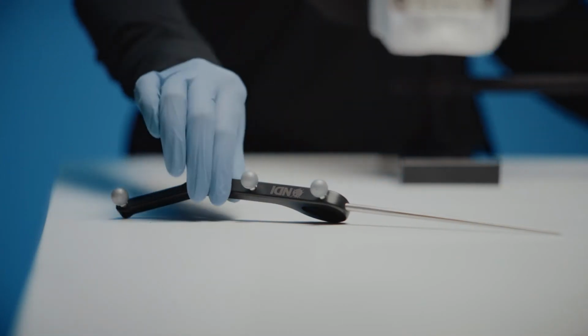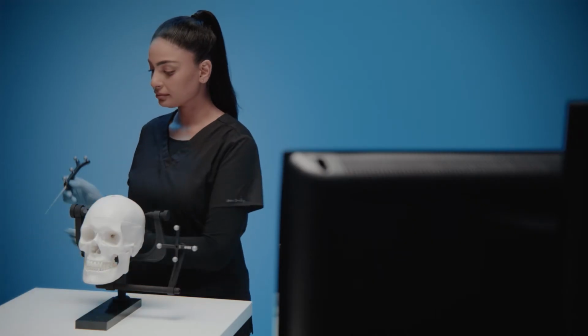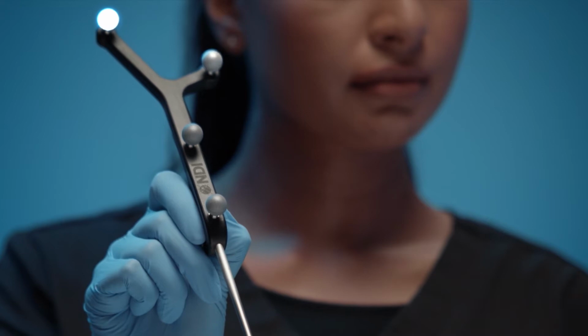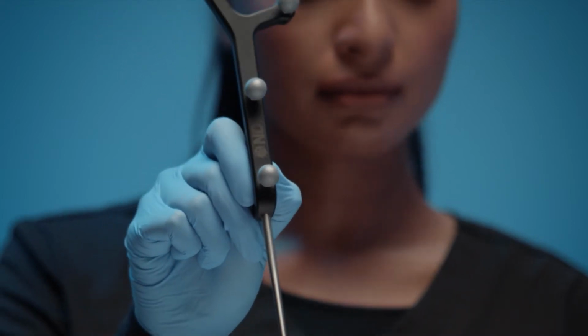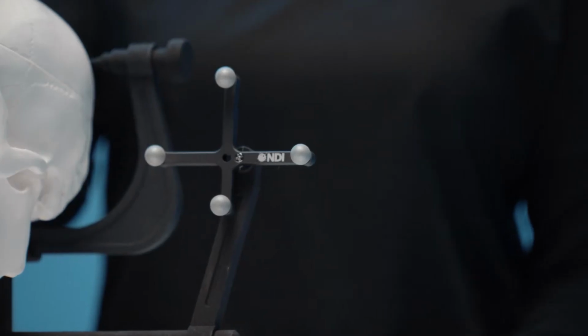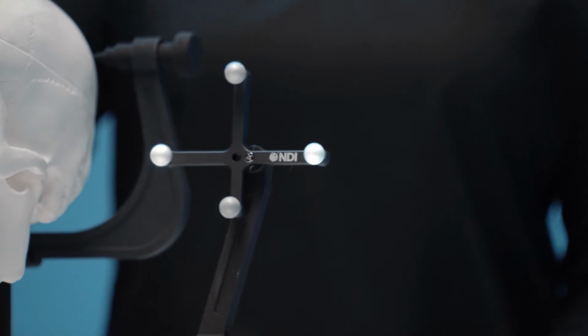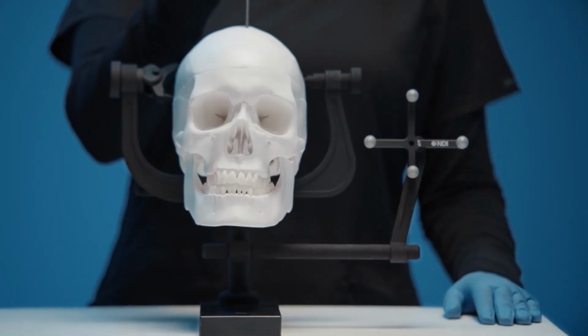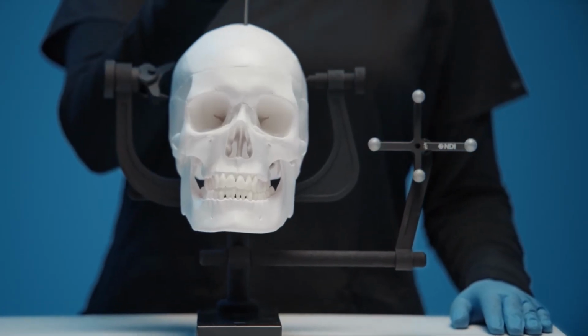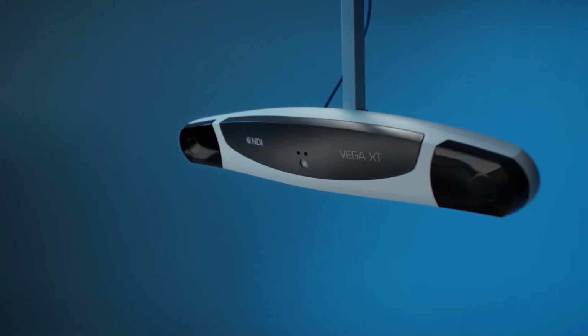Markers are attached to instruments for detection and identification purposes. They act as localization points within the measurement volume. A reference tool is placed near the patient. It establishes a fixed or home location against which the instruments are tracked.